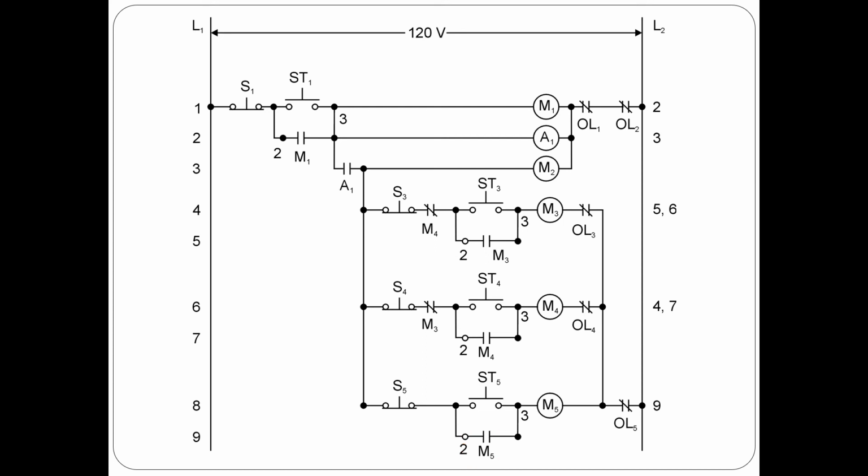Here's your next scenario. When I press the start button ST1, both M1 and A1 will start normally. However, M2 will not start. What is going to be the problem? Pause the video and see if you can figure it out.